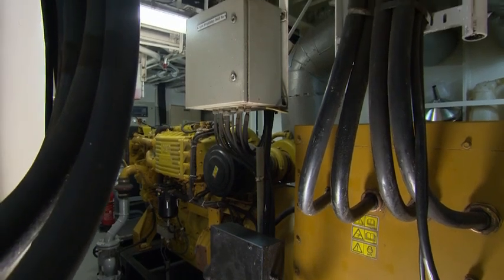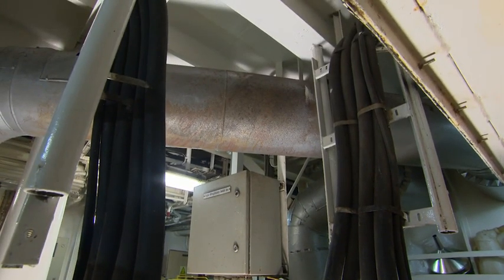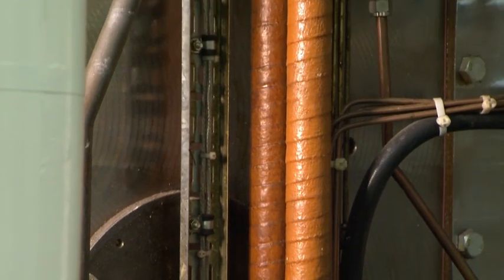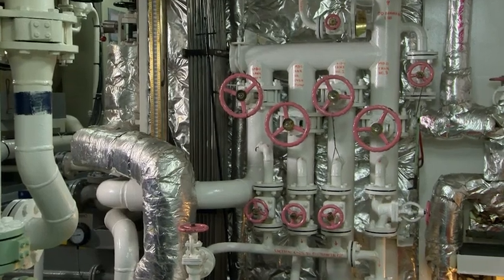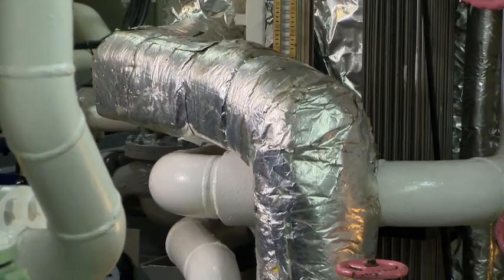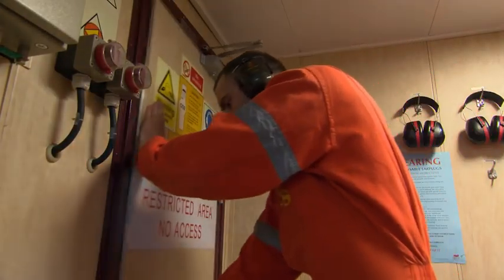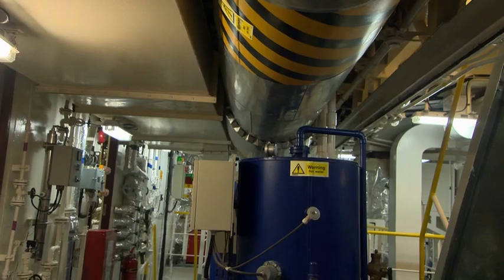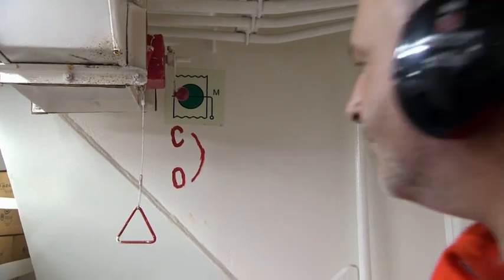These measures include running electrical cables through ducts to shield them from heat in the event of a fire, installing splash panels and double-skinned fuel oil pipes to protect hot surfaces from high-pressure pipe failure, fitting insulation to retard the spread of fire, and to provide additional protection for crew accommodation and cargo spaces, and providing fire-resistant doors, airtight hatches, and individually controlled ventilation dampers to seal off the machinery space and deprive the fire of air.